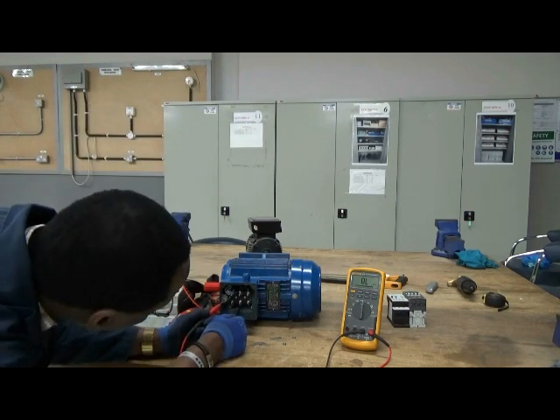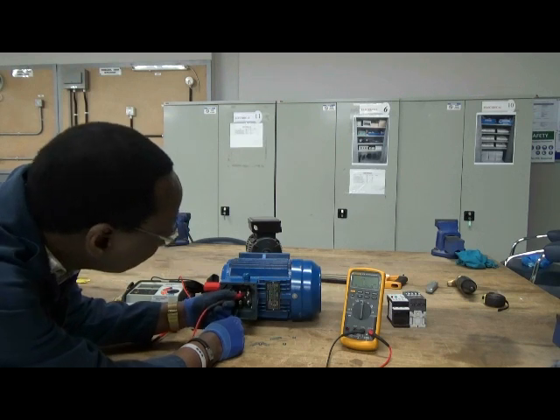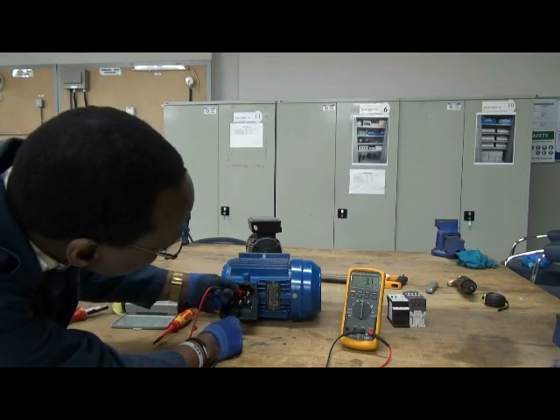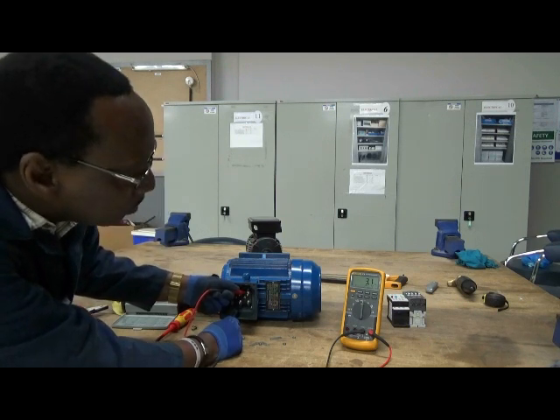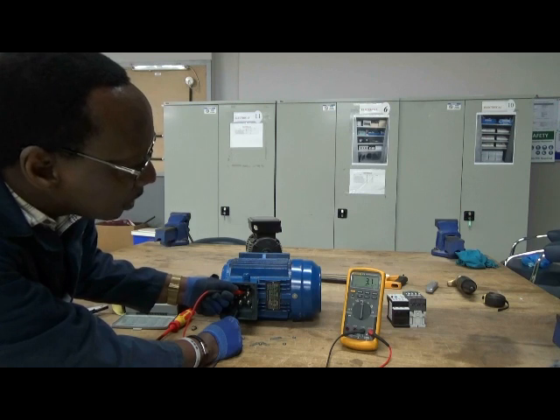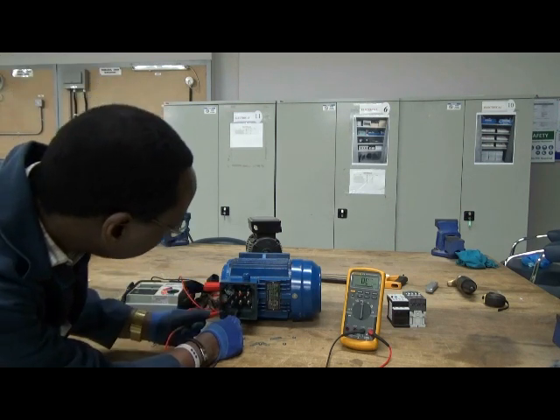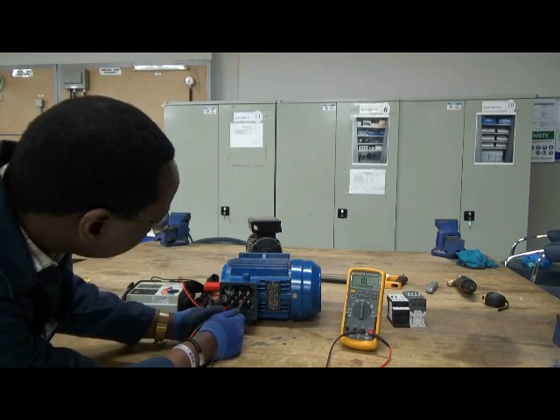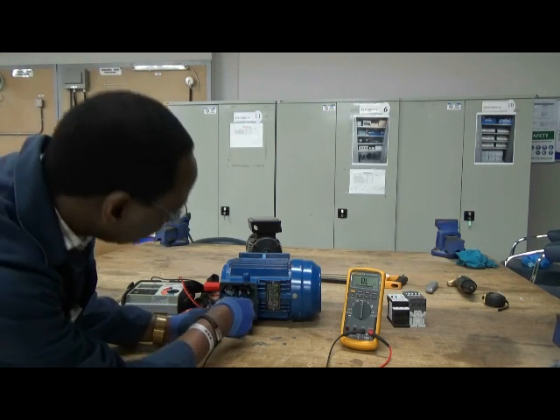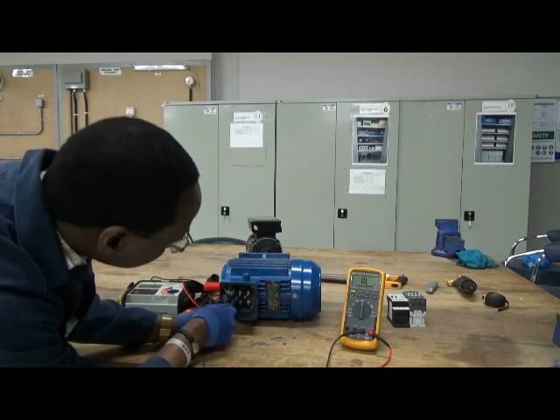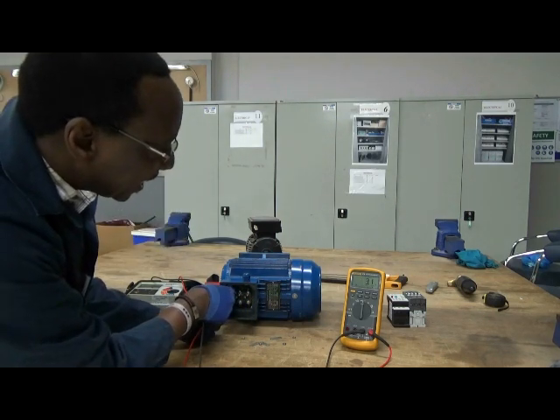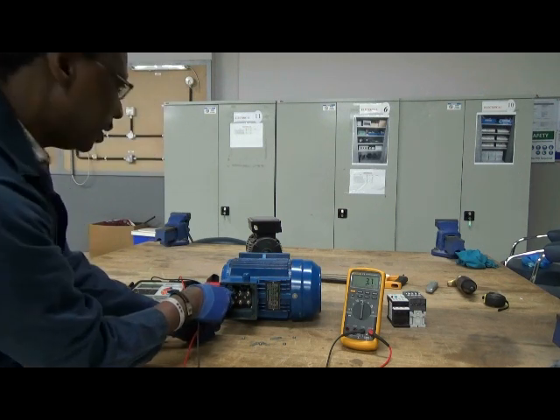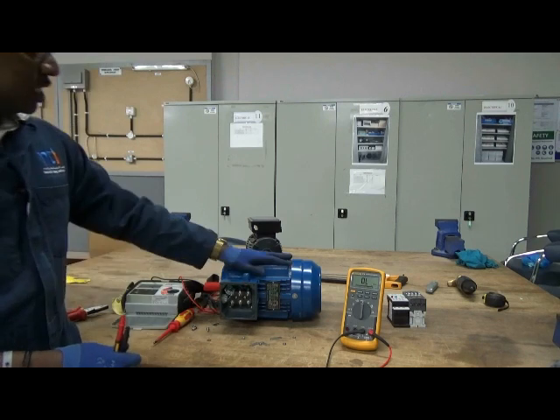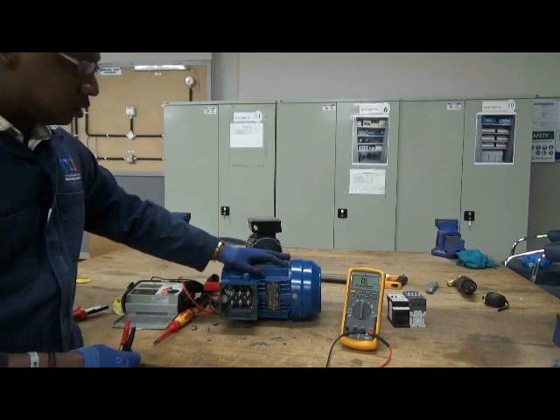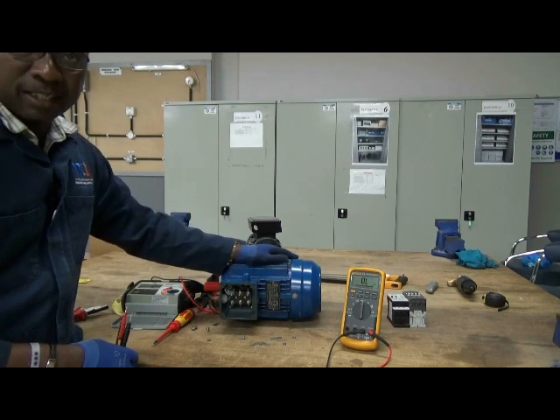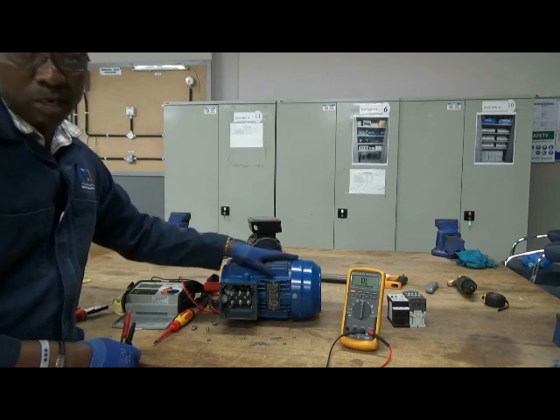So I'll now go on to look for the second winding, and fortunately it is the middle one and the end one right at the top there. It is giving me almost the same resistance again, 3.1 ohms. So I can go on to measure the last winding resistance, which is most likely to be these two here. Again, they give me the same reading, 3.1 ohms. It means the resistance of the stator windings here are balanced because they are of the same value, all of them.